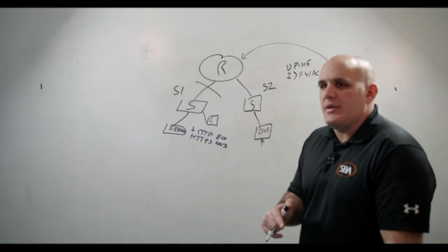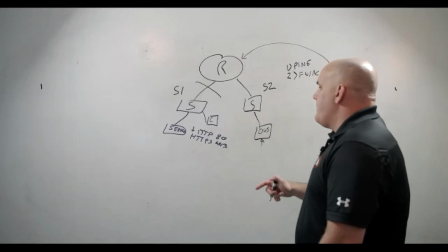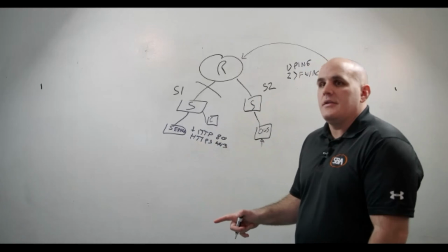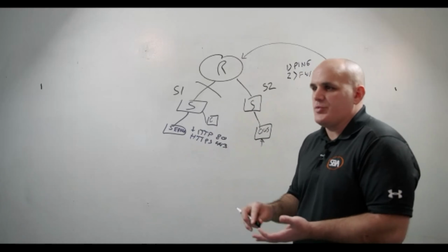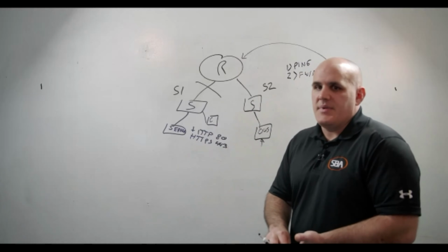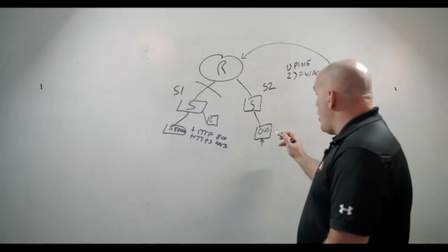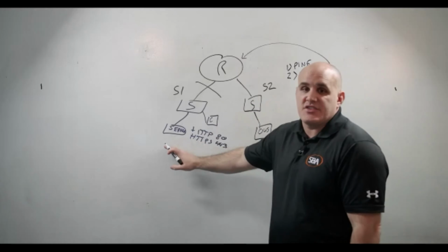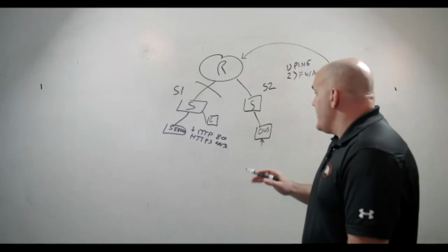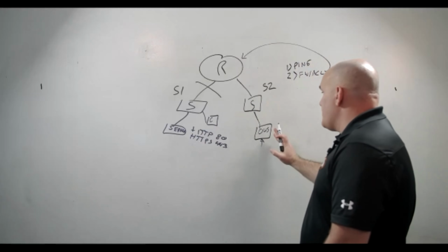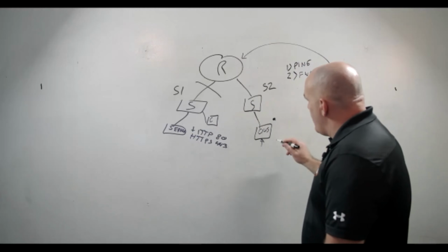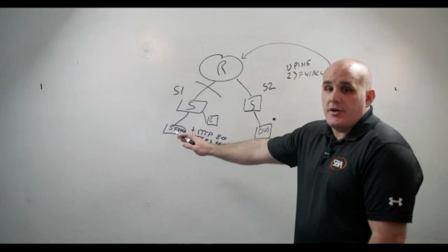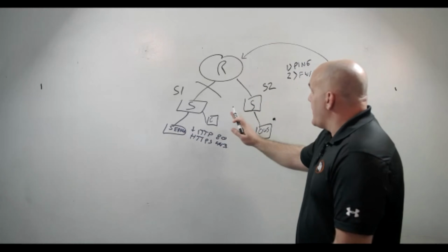If you can log in with your administrative account, but the user cannot log in with their account, then it's most likely a password or a user right issue, because that tells you. So, log in from the operator workstation to the server, Ryan. Good question. If you're able to log in from this operator workstation over here to the server, then that tells you.